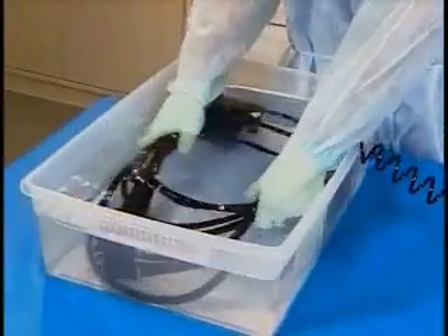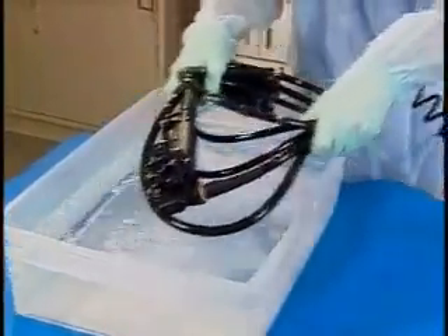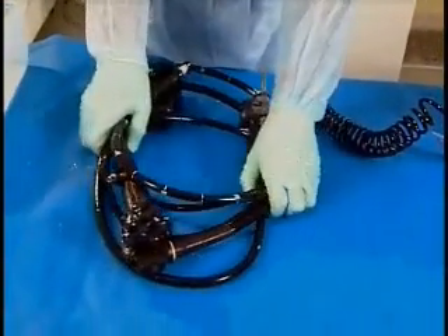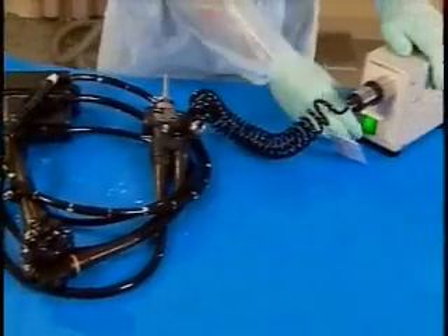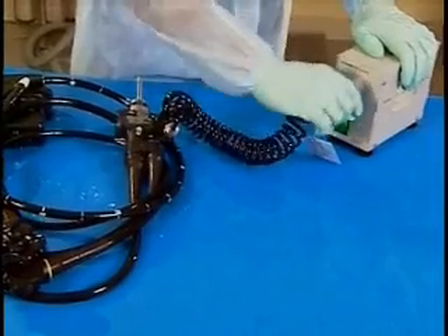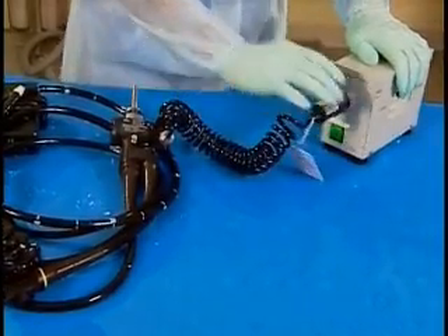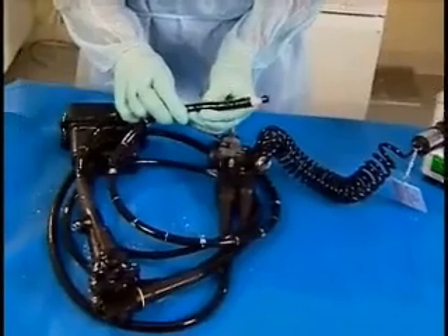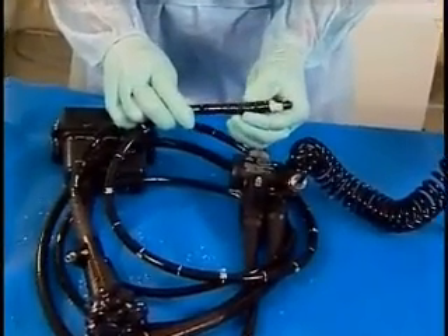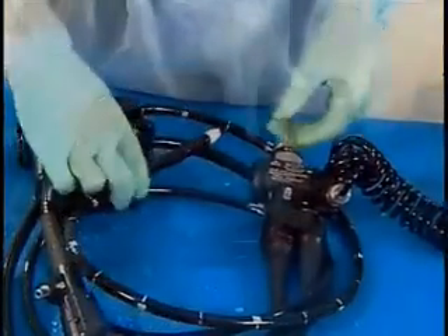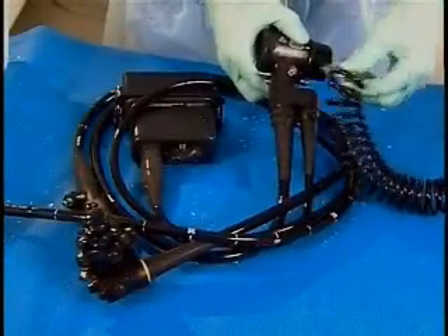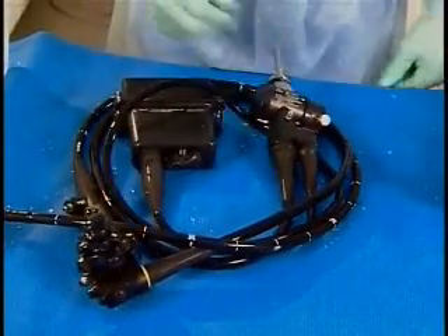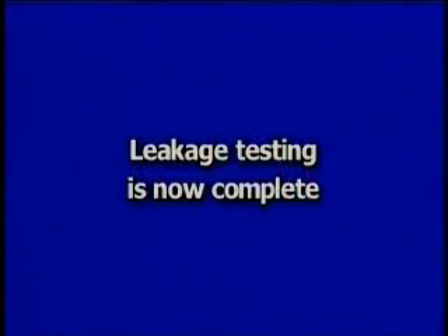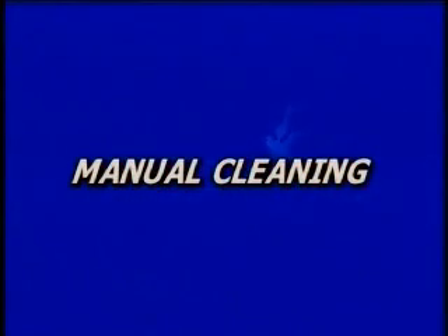If no leaks are observed, remove the endoscope from the water. Disconnect the leakage tester from the air supply and wait for the bending section to return to its normal size. Detach the leakage tester from the water-resistant cap. Leakage testing is now complete. The next step is to manually clean the endoscope.